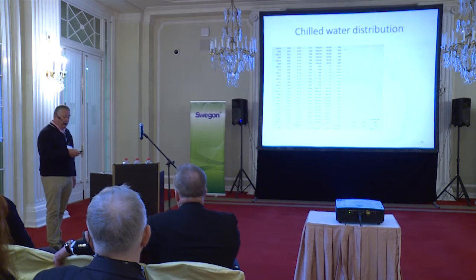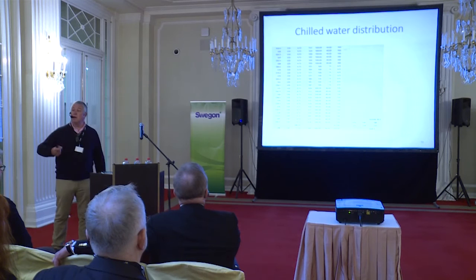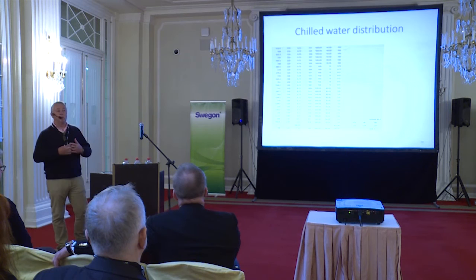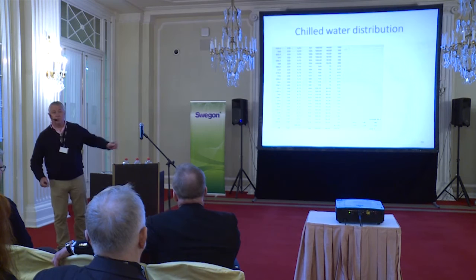What we're looking at here is these different numbers, because ASHRAE 90.1 says whatever size your plant's going to be, you cannot use more than this many kilowatts of power to actually move the water around. So we've got to start looking at where we're going to be and what the pumps are going to be in efficiency.